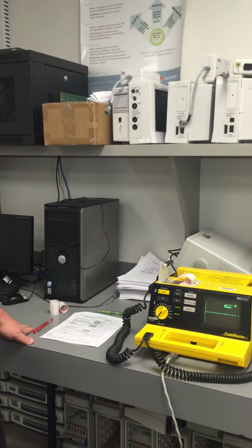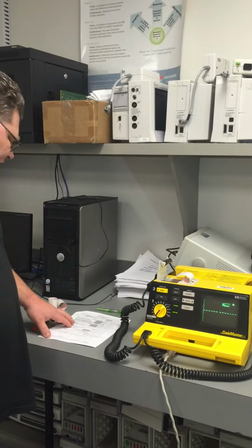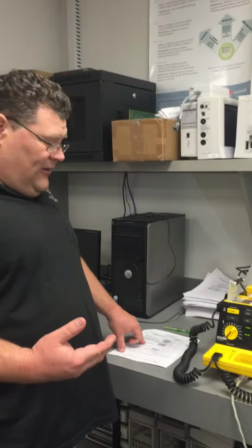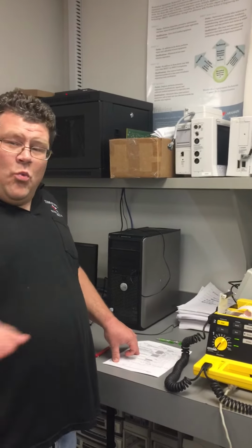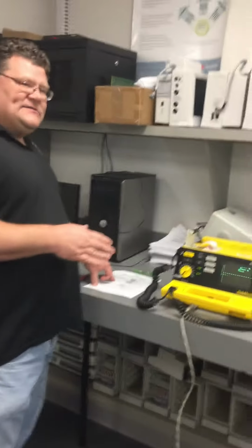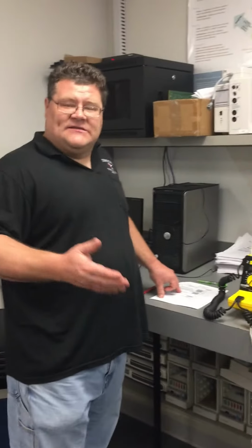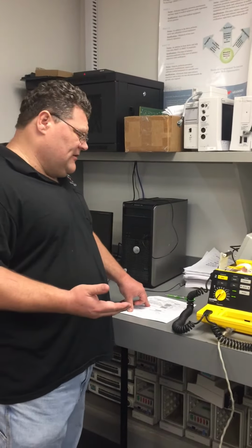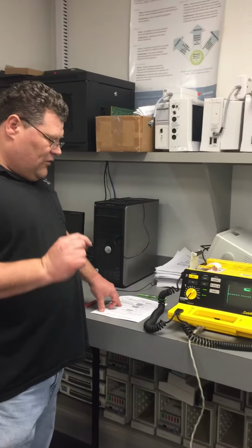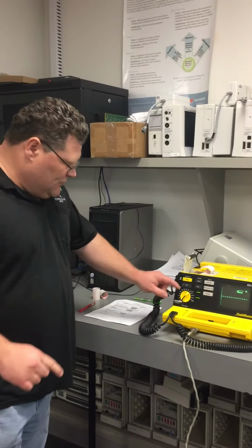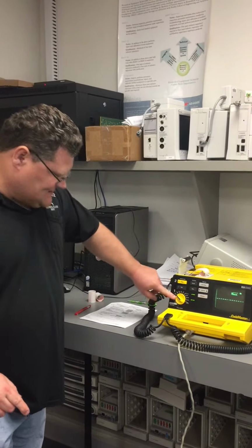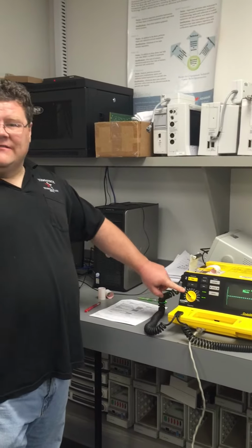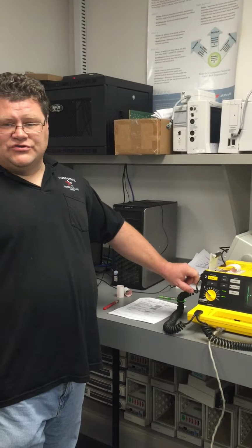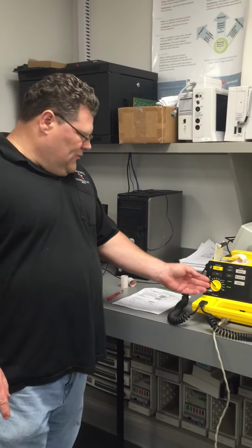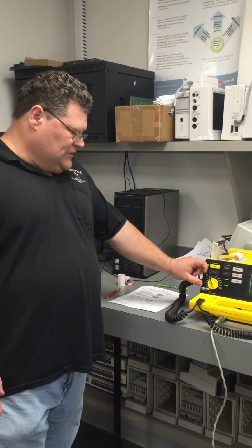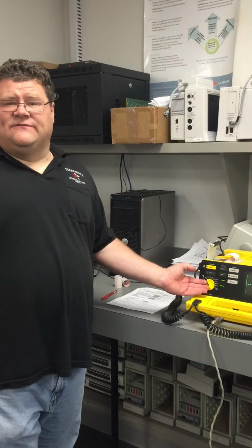Now the next one is the output energy. The output energy is sort of funny because a Defib actually has a very wide range of error. It has much more than 10%. It actually has a 15% error range, or 4 joules, whichever is greater. The reason is that for people testing at 10 joules and less, they actually have to have a 4 joule energy range. Once you get over 20 joules, it's actually best to use the 15%.